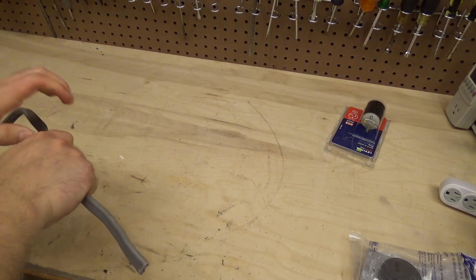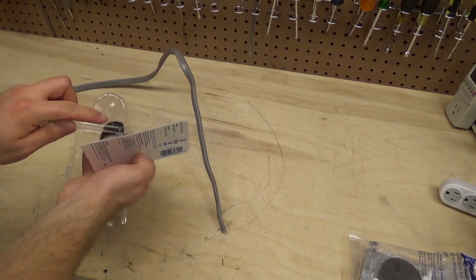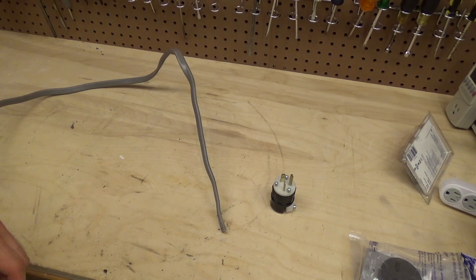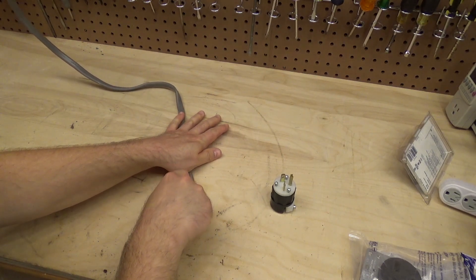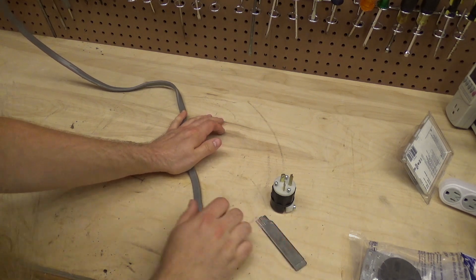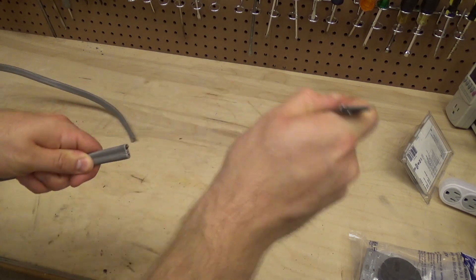What I'm going to do is put a 20-amp plug — I have a 20-amp socket in the garage — on this wire, and on the other end we're going to put a 30-amp outlet, which is incorrect and unsatisfactory for any long-term installation. This is only for a test. If you have a 20-amp outlet and want to install something that's 30 amps, you have to change it — the plug size is different for a reason. The 30-amp is supposed to have 10-gauge wire; the 20-amp is only 12. It's a short run so I'm not worried about it for the test.